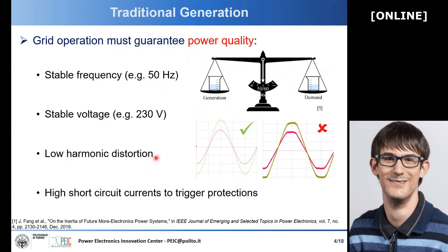We also require high-quality voltage both in terms of amplitude and in terms of harmonic distortion — so we want a clean sinusoidal waveform. And finally, we also want very high short-circuit currents in case of short-circuit faults, because we want to trigger protection devices to isolate the fault, clear it, and solve the issue.